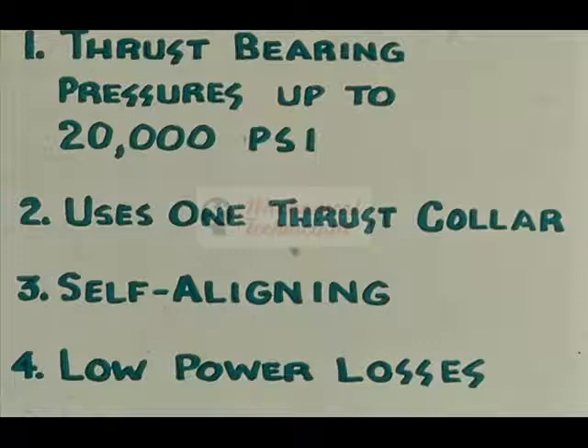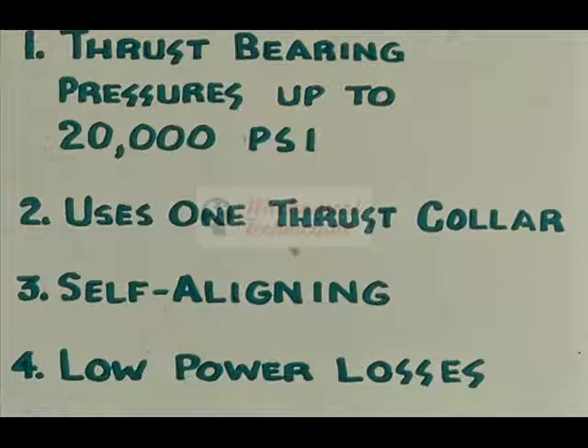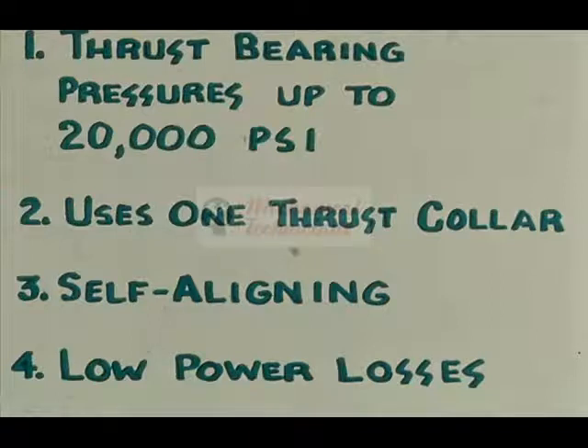The Kingsbury thrust bearing eliminated or reduced many of the limitations imposed by the old collar and block system. First, it permitted thrust pressures on the bearing to increase up to 20,000 pounds per square inch of projected area. Second, it permitted the use of a single thrust collar. Third, the bearing was designed to be self-aligning with each bearing face carrying its share of the load. Fourth, horsepower losses in the bearing were reduced to about 5% of the old values.